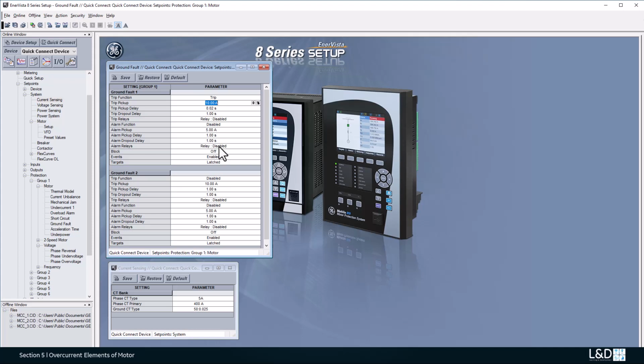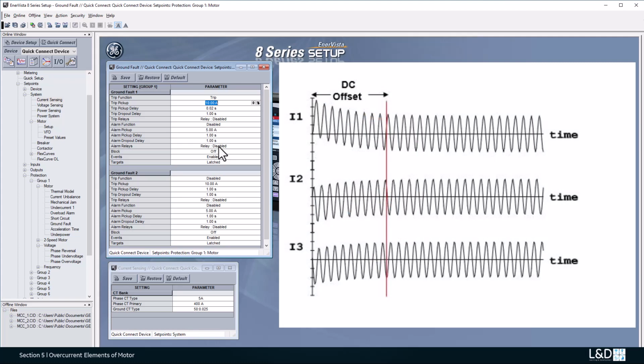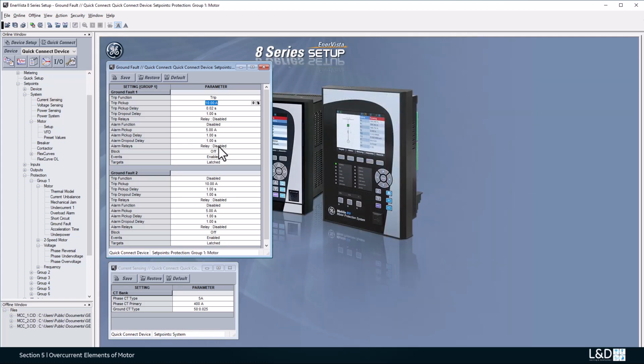The slight mismatch of the differential CTs, combined with a relatively large phase current magnitude, produces a false ground current even when the three phases are balanced. So the pickup level should be set higher to disregard this error. When the motor starts, the starting current, typically 6 times FLA for an induction motor, has an asymmetrical or DC component. This momentary DC component causes a net current into the ground input of the relay.